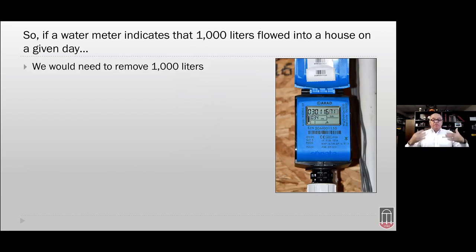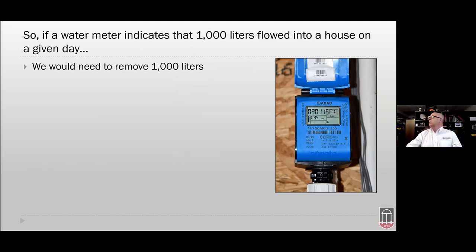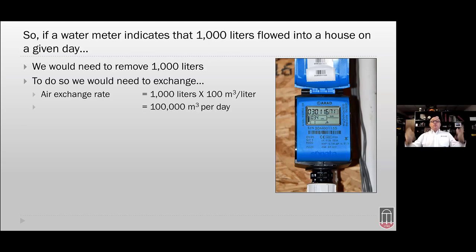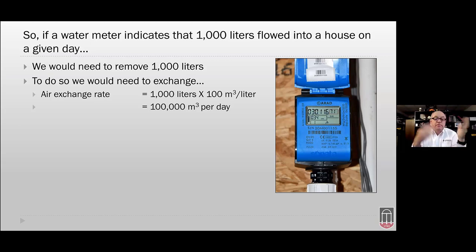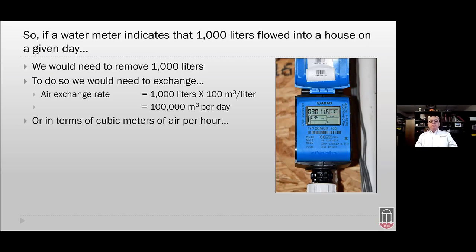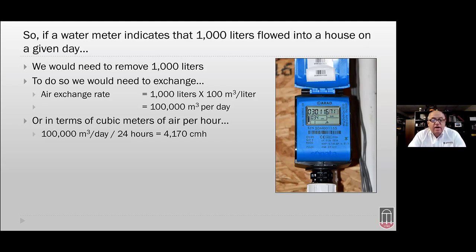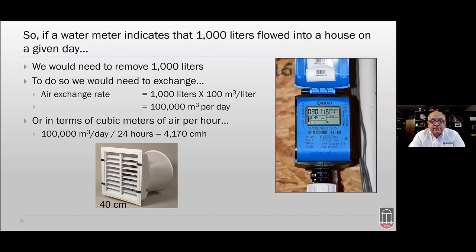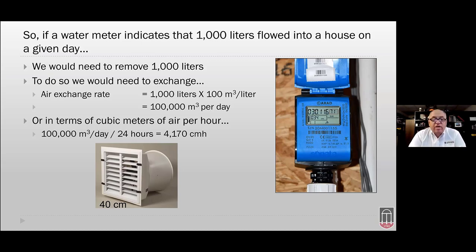If a water meter indicates that a thousand liters of water flow into a house on a given day, we simply have to ventilate to remove that thousand liters — we add it, we remove it. So we need to exchange 100 cubic meters per liter: 1,000 times 100 equals 100,000 cubic meters of air per day, or divided by 24, that's 4,170 cubic meters per hour. We would need to operate essentially a 40-centimeter fan constantly to remove a thousand liters of water using that rule of thumb.